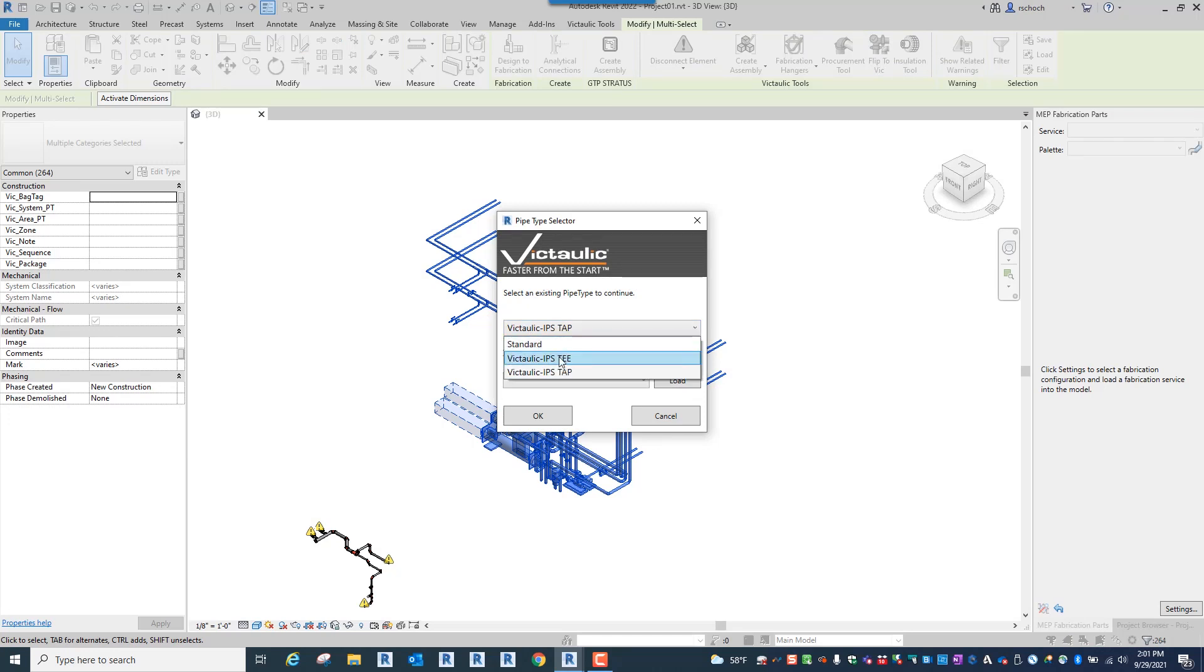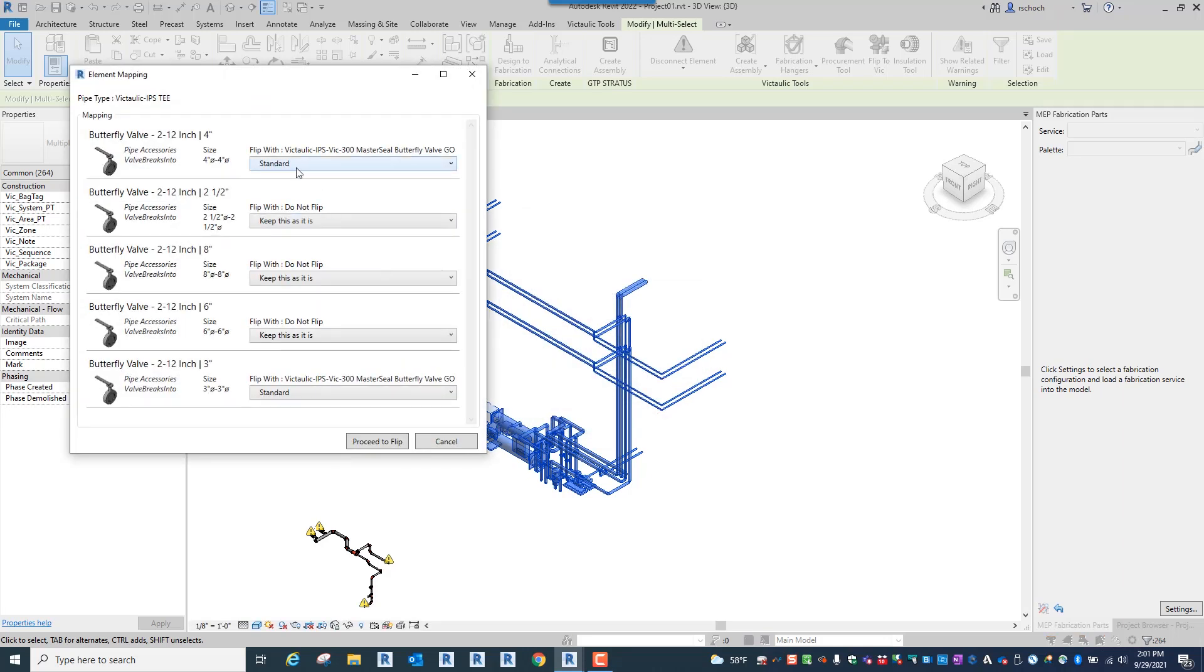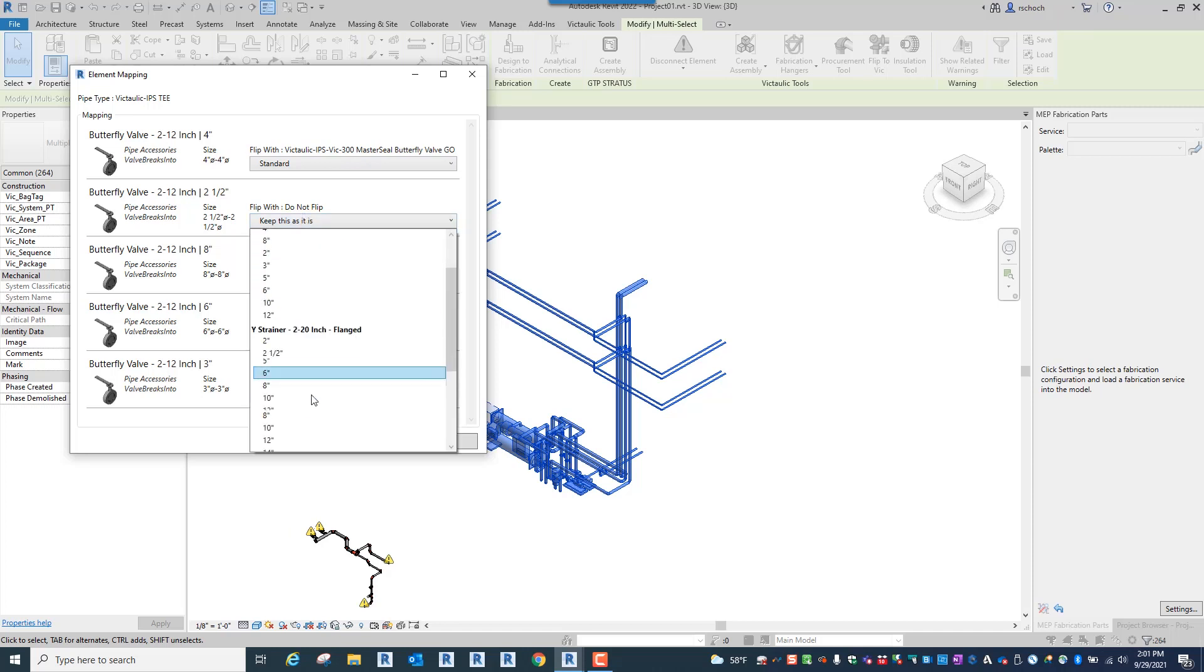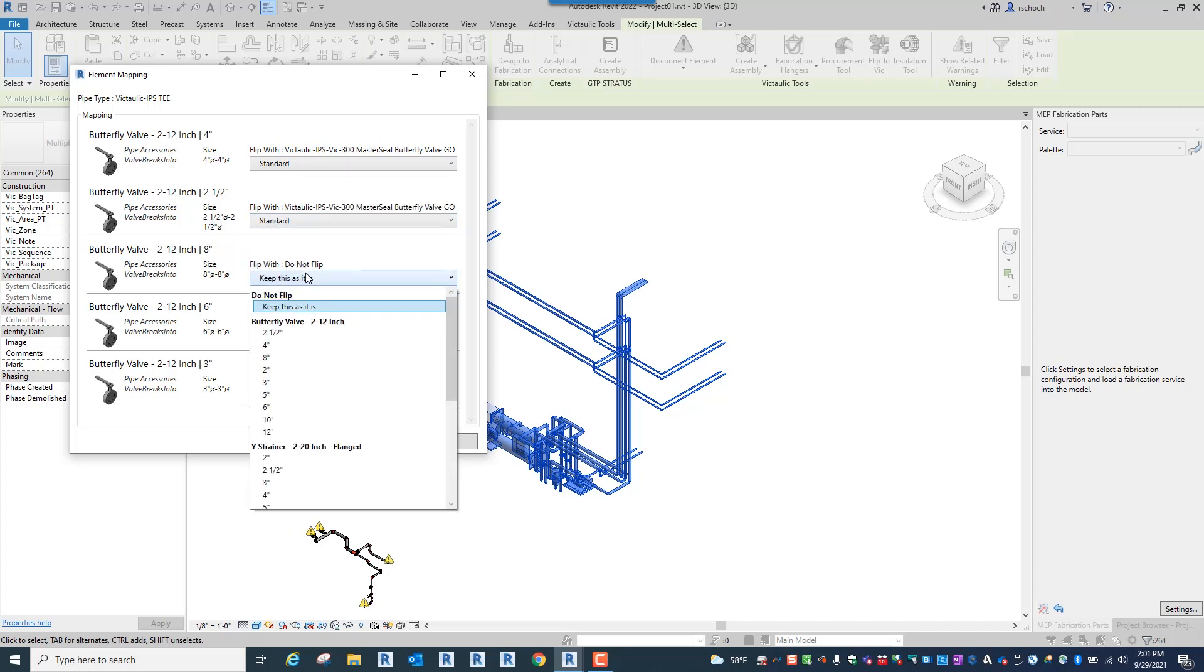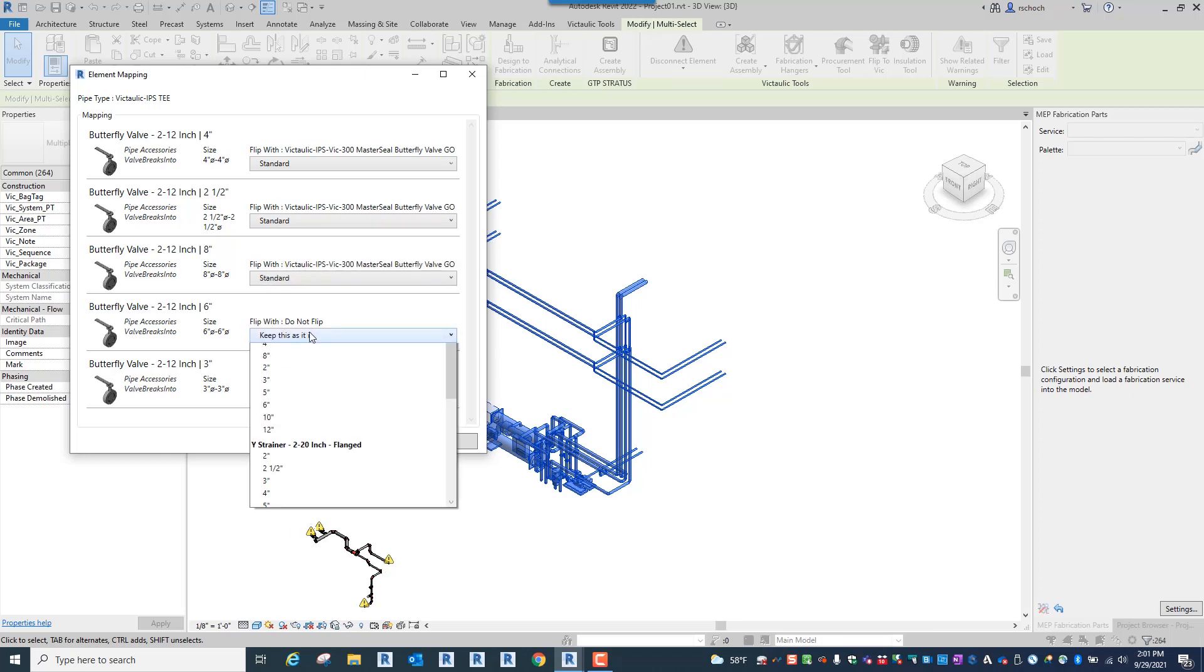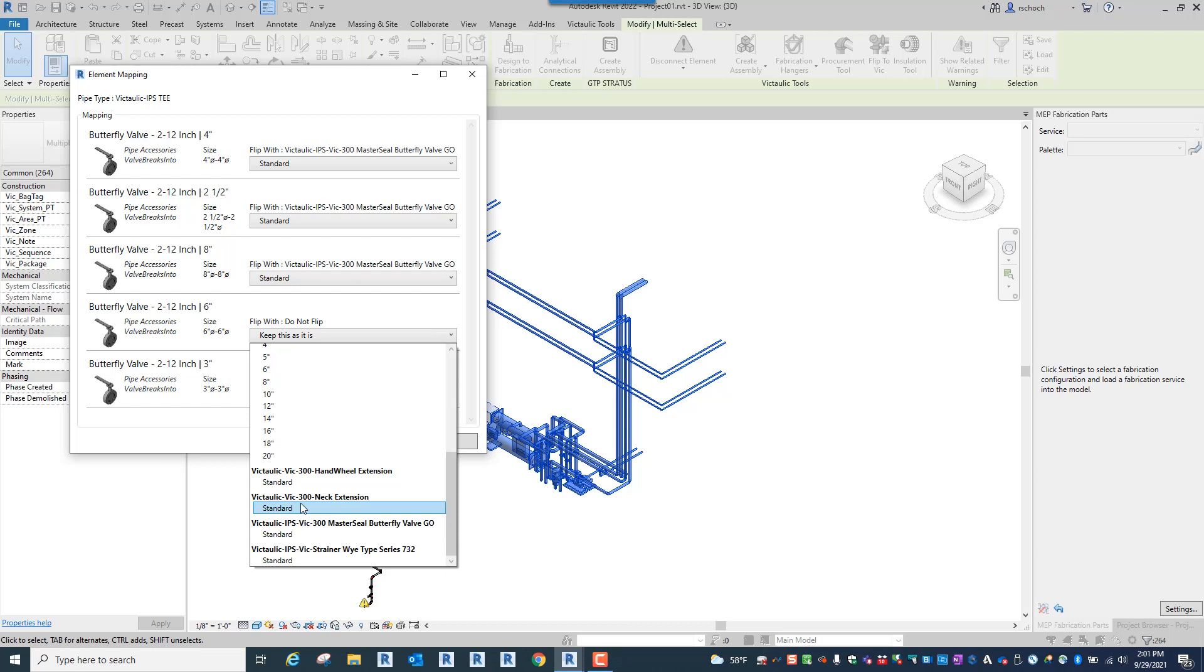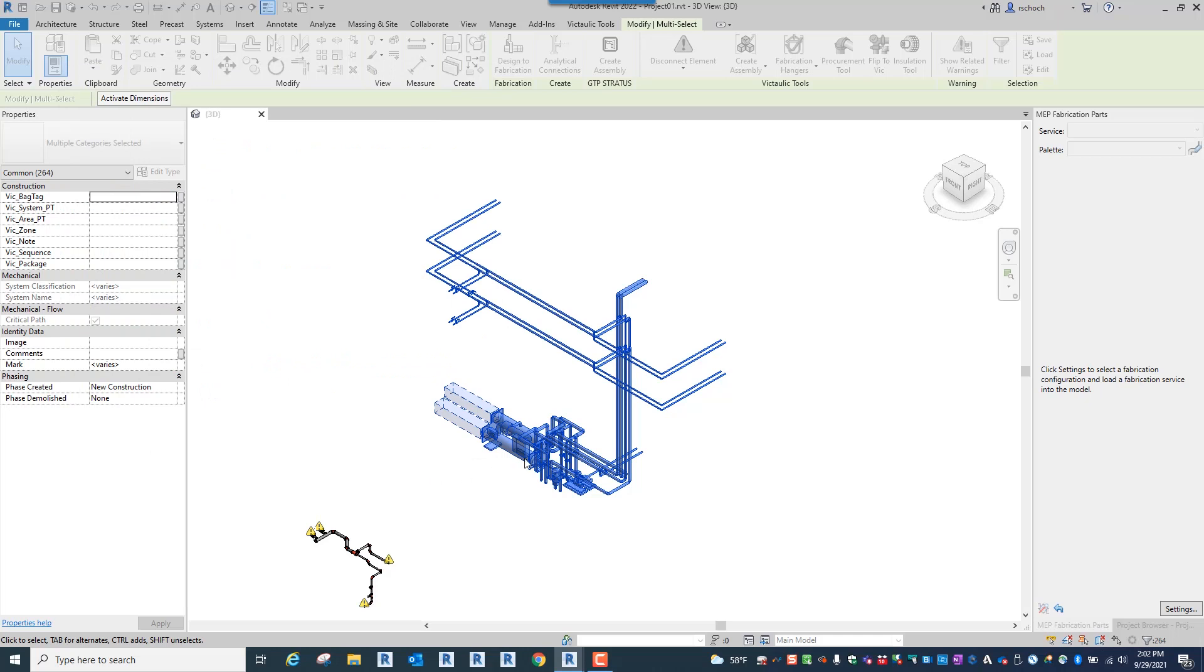I can see that I want to flip it over to the tee pipe type and I can click OK. Here's all the different options. So I can come in here and specify the valves that I want for each size. Now when we build our butterfly valves we make them that they're lookup table based which is a little odd for Revit. Most valves you'll find that are generic from Autodesk are going to be type based. So just be aware you may have a lot of accessories on the left here because they're based on size and you can easily just map those to probably one of our families. So it makes it super simple. So I'm going to proceed to flip and now in a few moments you're going to see this entire model change over.